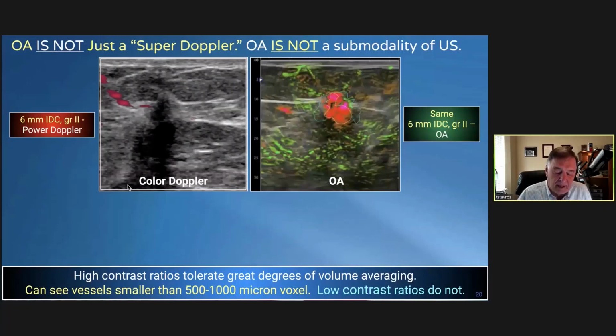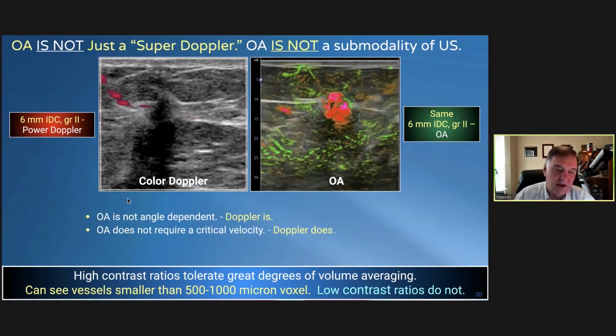Now, people want to think about OA as being a super Doppler, but it's not at all like Doppler. The only similarity is that they both show blood vessels. But Doppler has several limitations. It's angle dependent, whereas OA is not. Doppler works best at 0. It doesn't work at all at 90. OA doesn't care about the angle of incidence. Doppler requires a certain critical velocity. If blood flow is too slow, you can't see it on Doppler, like you can't see a Doppler signal in a placental lake, but you can see the flow on grayscale.